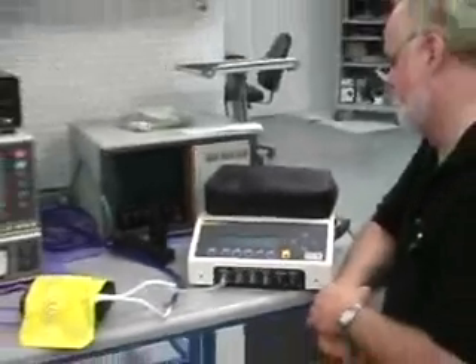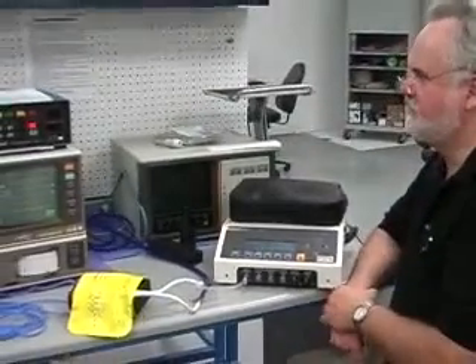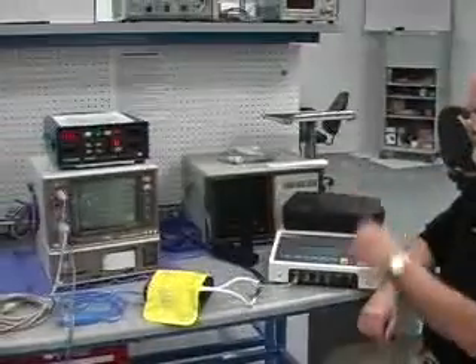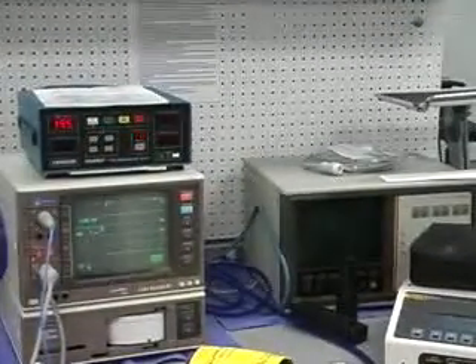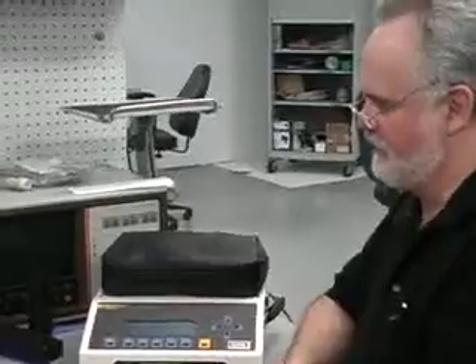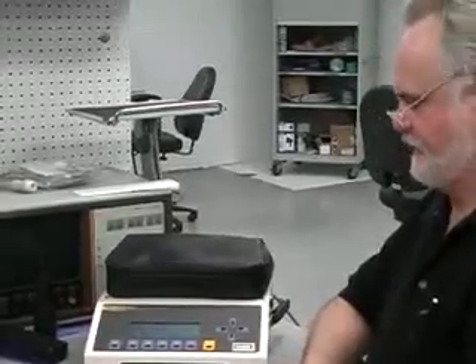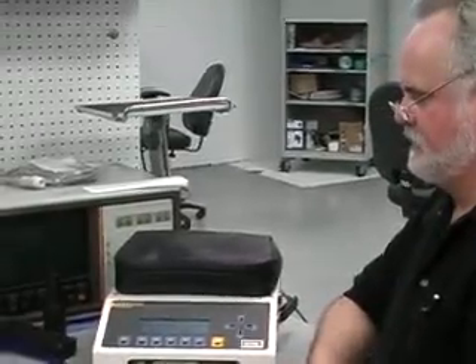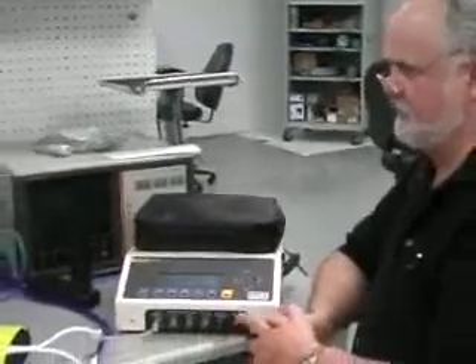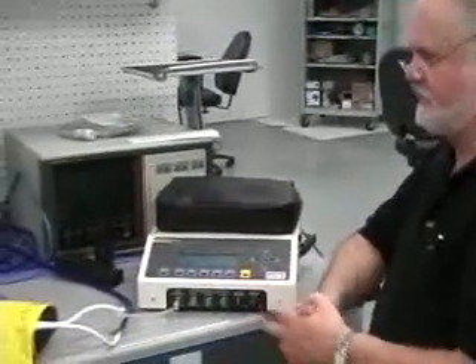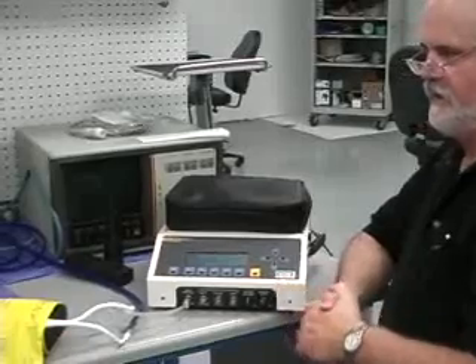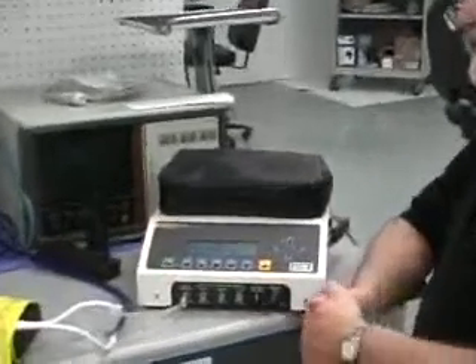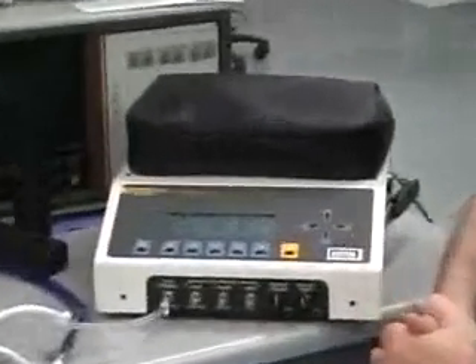So again, we're reading about 194 and 195 on the unit. So to do this test before, you'd have to have a manometer and a stopwatch and a pencil, and you have to be watching it. So what we've done is fully automate that test for you, make it a lot easier. So these tests, along with the dynamic tests that this device can do, will also be able to be controlled via the med tester also.